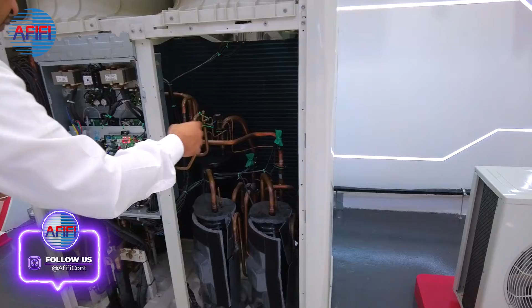You'll have one compressor. By the way, are your cycles two different cycles, or one cycle with two compressors? One circuit, one full circuit with two compressors. This is called the tandem structure. And it's so dangerous. If one compressor burns, it will kill its brother. So there are some protections for it in VRF. How do you protect it?